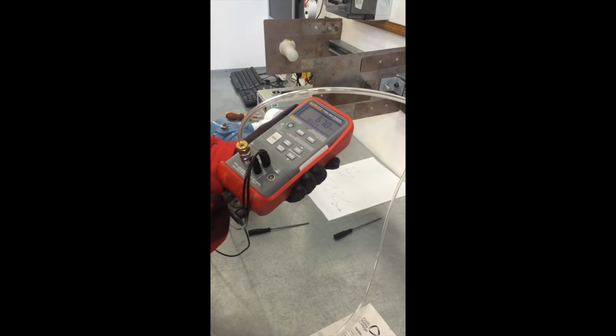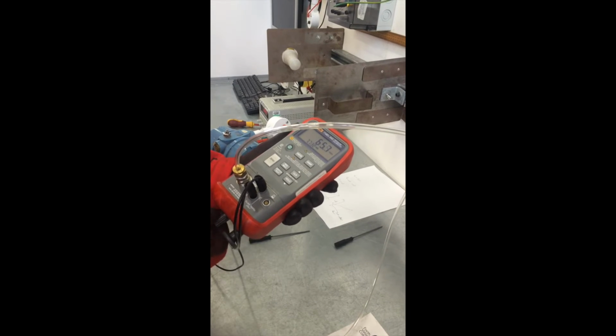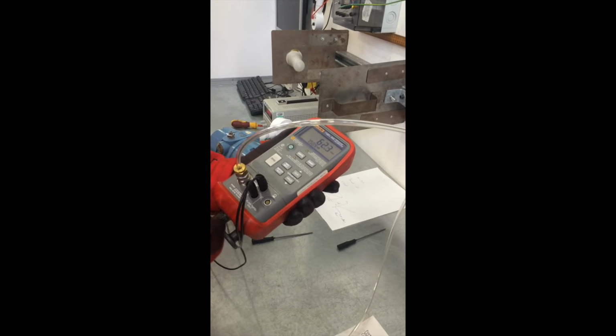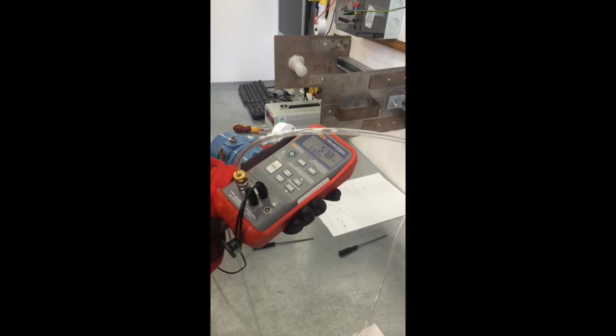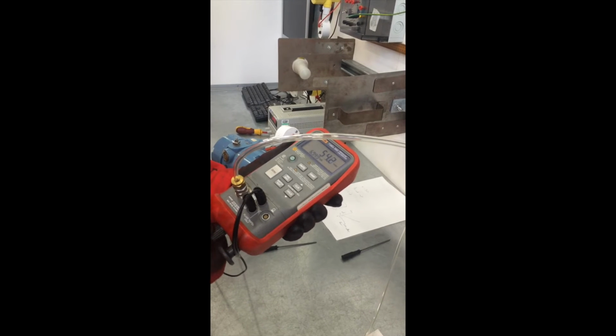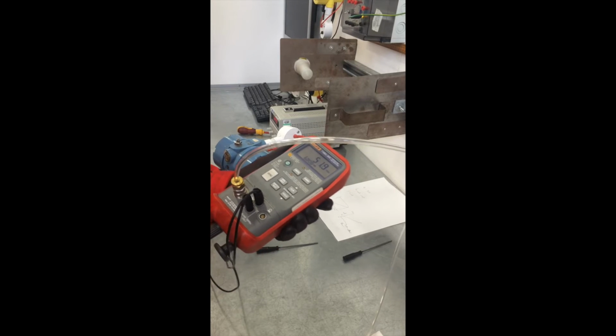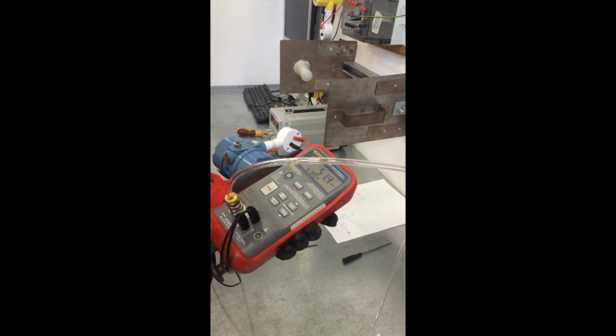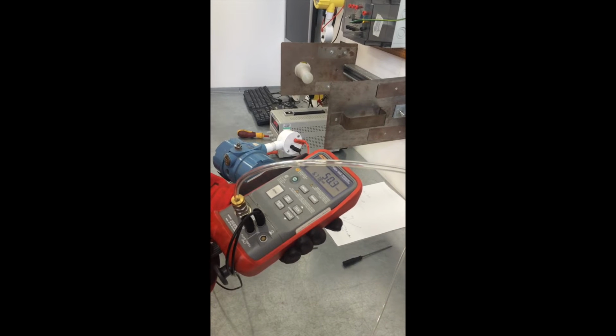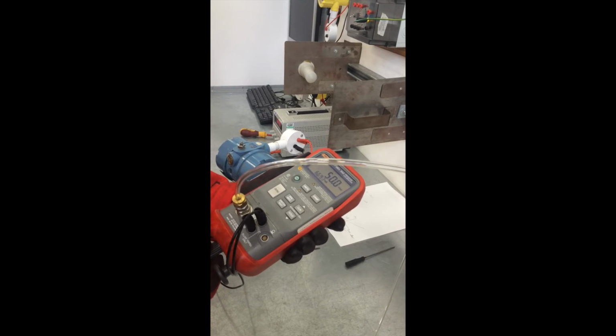After you've checked that, you then pump up to 50 millibar using these controls here. You can use the pump to move it up a bit, and then you use this wee dial here to do fine adjustments. You can see I'm up at 60, so move it back down to 50. I should just mention as well, this DP cell's leaking a wee bit, so it bounces up and down on the pressure inside it, so you just get it as close as you can, but that's sitting okay. So at 50 millibar, it's sitting at 6.685, so you write that down in the actual output.